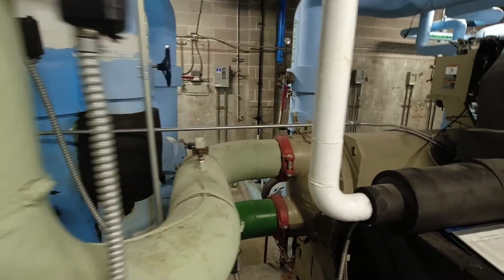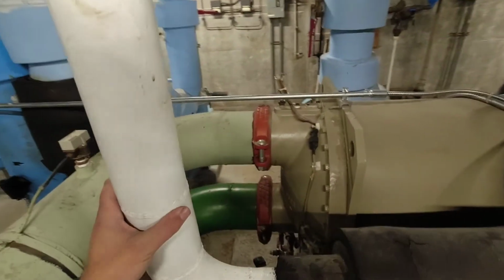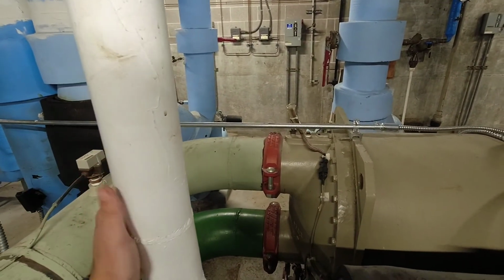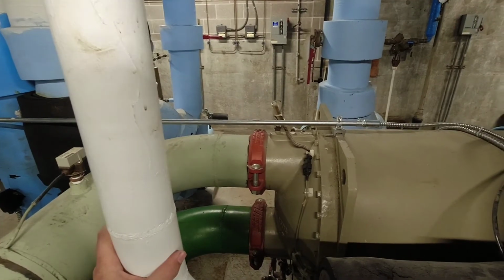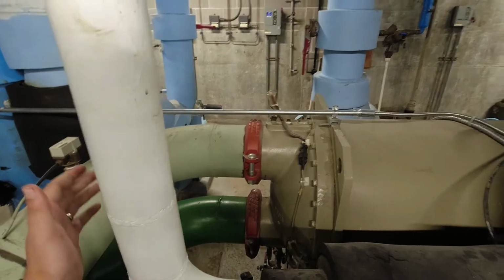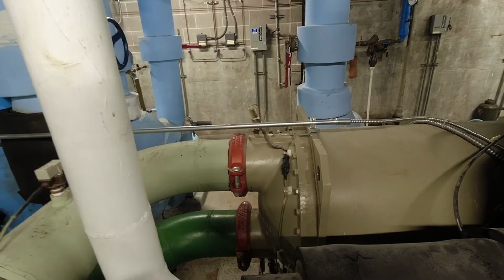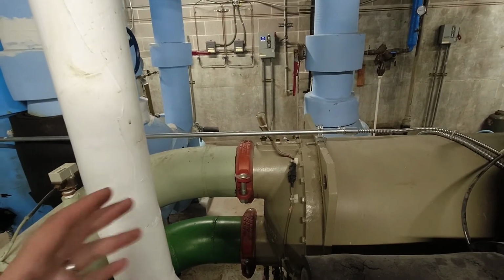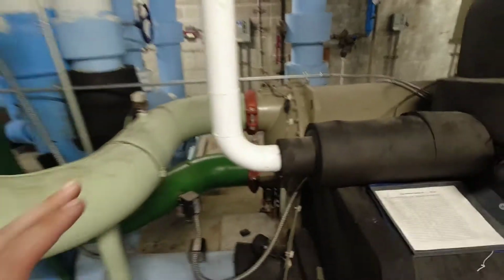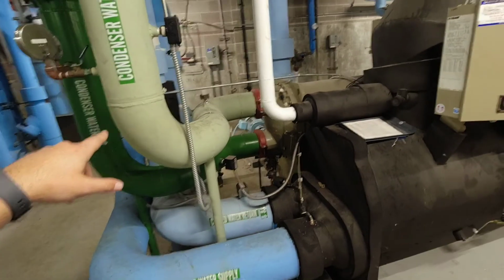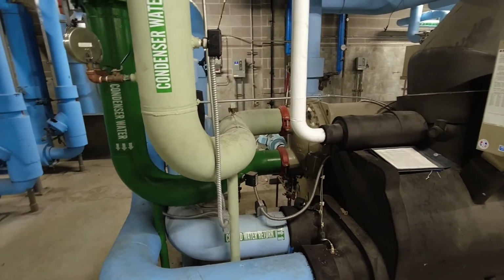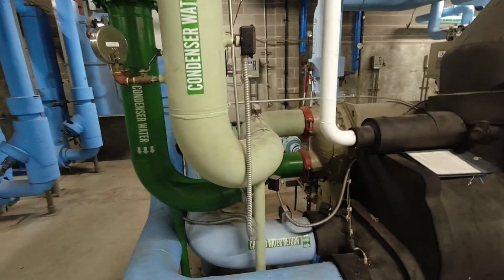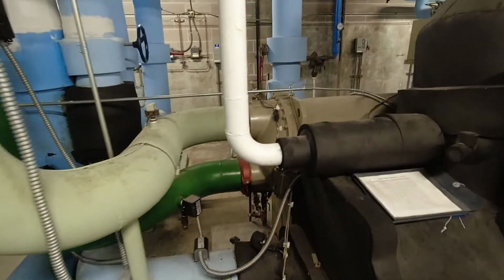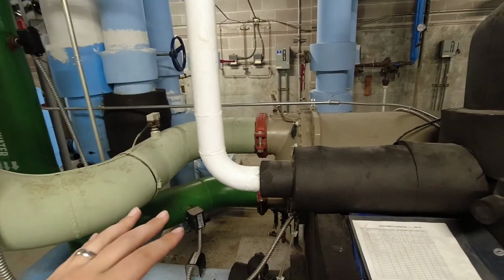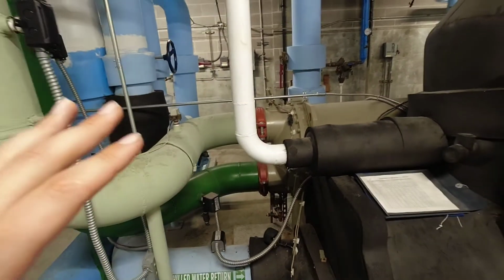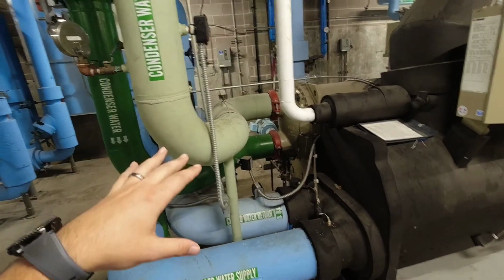Then you have your condenser water temperatures, and depending on your area and where you're set up will depend on how you can maintain and control those temps. But typically, the lower the temp you can maintain within reason, the better. Usually on these CVHE's and F's, I like to try to run about 70-degree water. Sometimes I'll let it go down to 65, but in my personal experience and the way most of my plants are set up, they do better at 70 degrees.